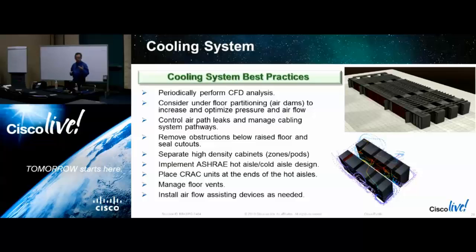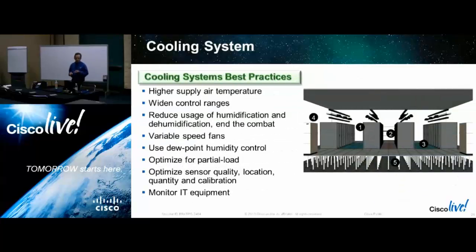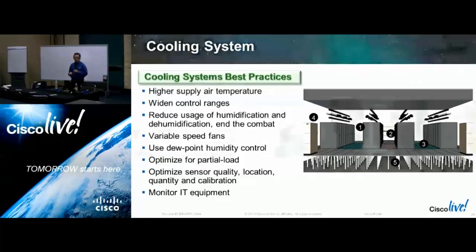We talked about air path control, underfloor air dams. The ASHRAE limits on the set points of your data hall were broadened a few years ago. When you do your command and control in the data hall, you want to make sure that you apply those to the appropriate places of your command and control system. As you replace fans and pumps, go with variable speed that are manageable, because that's how you're going to economize over time. Monitor, optimize, manage baseline. Very simple. It's the way you do almost any kind of a hard stat metric.